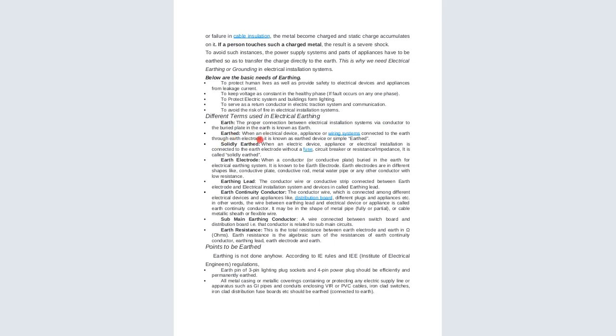Earthed means that when an electrical device, appliance, or wiring system is connected to the earth through an earth electrode, it is also known as the earthed device or simply earthed. Then we have another term, solidly earthed. What does it mean? When an electrical device, appliance, or installation is connected to the earth electrodes without a fuse, circuit breaker, resistance, or impedance, it is called solidly earthed.